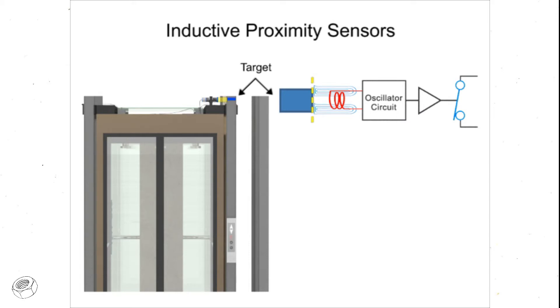These eddy currents induce a power loss within the oscillator circuit, and in turn cause a reduction in the amplitude of the oscillations. This is known as the ECKO, or eddy current killed oscillator, principle. This change in amplitude sends a signal to the switch, changing it to its normally open or normally closed configuration, respectively.